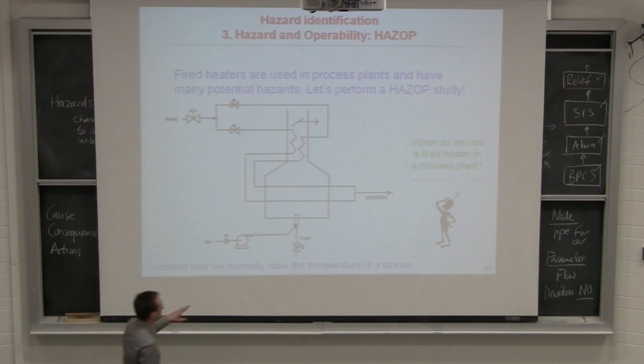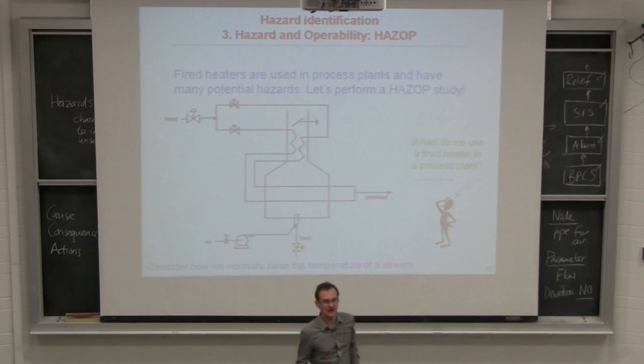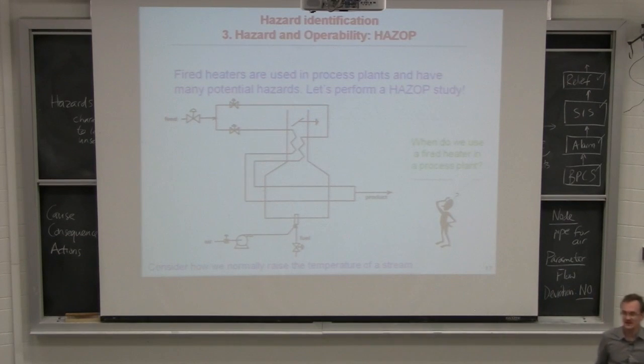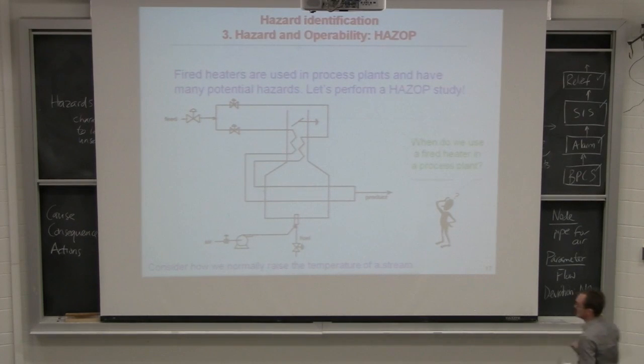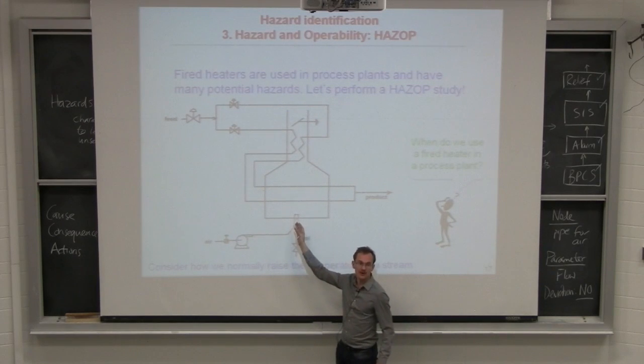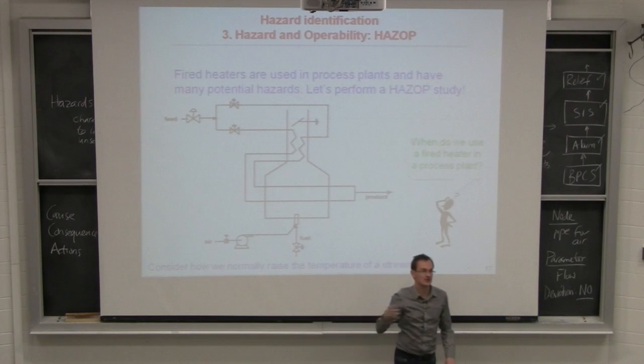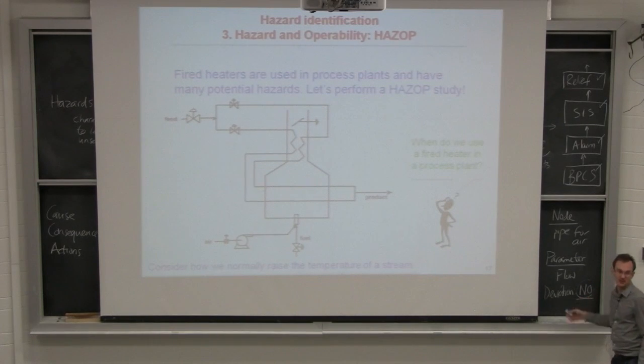Okay, you could have an explosion, or there's going to be some leakage through that fired heater, so you are going to get some form of air in there and start to explosively ignite that fuel source. Okay, so the fuel valve is open. These fired heaters are not totally insulated, right? There's gaps in there, and air can leak in and set off as an ignition source. So your fuel can go directly to the fuel into your stack. Okay, so emissions of the fuel outside, but then leading to the same outcome. Okay, so that would be the very initial, if that air stops flowing. Initially, you just form carbon monoxide, but then later on, because you've got no air to support combustion, there's no CO being formed. But that would be a perfect example for low flow.